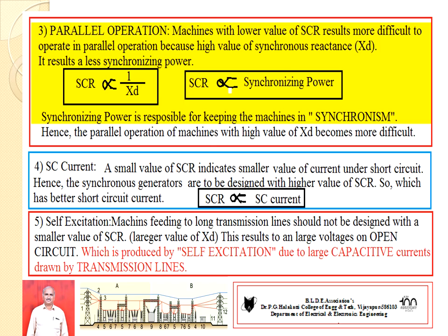Number five: Self-Excitation. Machines feeding long transmission lines should not be designed with a smaller value of SCR. A smaller value of SCR results in a larger value of XD, which results in larger voltages on open circuit produced by self-excitation, due to capacitive currents drawn by the transmission lines. These are all the factors that affect the performance of alternators or synchronous machines.